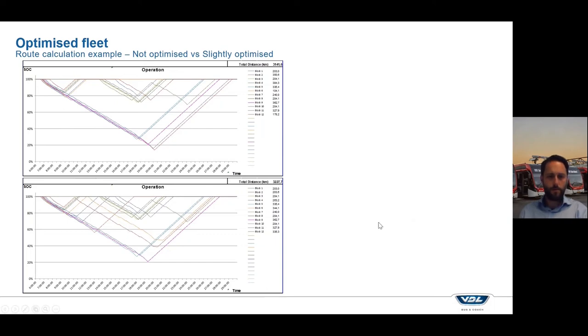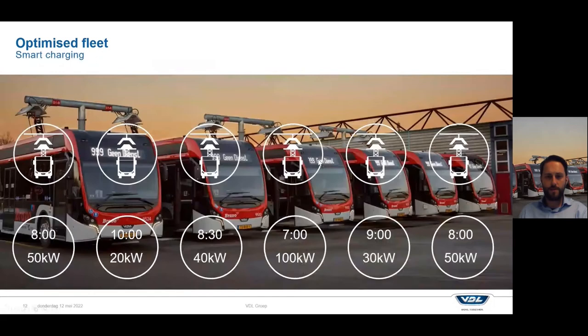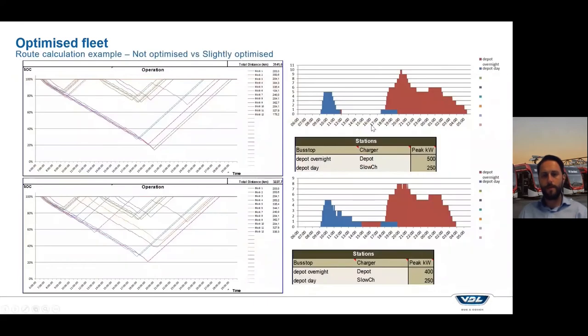Then, secondly, what I also did is I delayed the charging sessions. And that's something that you can see on the charging operation. In the original version, we used 10 chargers during the afternoon session. Now we only use eight chargers. And this is mainly because I have delayed the start of the charging session of the buses.